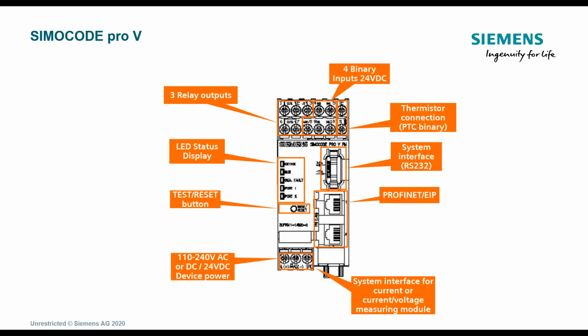So for my little pump panel application for the potato farmer, the one output went to the NEMA contactor for pulling in the pump, and the other 2 outputs were there for the light indicators on top of the pump panel. Yellow for saying, hey, you might want to come out here and check things out, and red means I've stopped and something's majorly wrong with his irrigation system. It does have 4 24-volt DC inputs. And if you remember, I said it has its own 24-volt power supply on terminal block 8. I could take this 24-volt power supply and go out and excite my HOA and my start-stop buttons locally at the motor MCC bucket or the motor control panel.